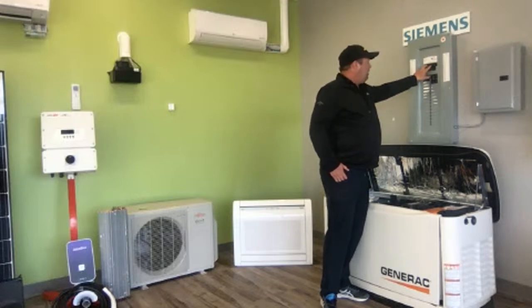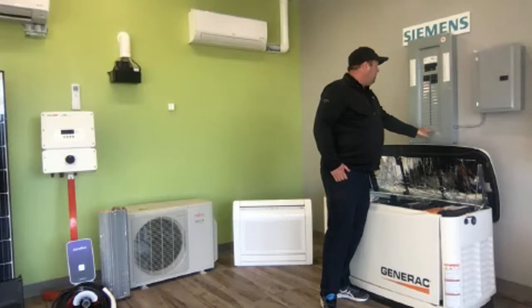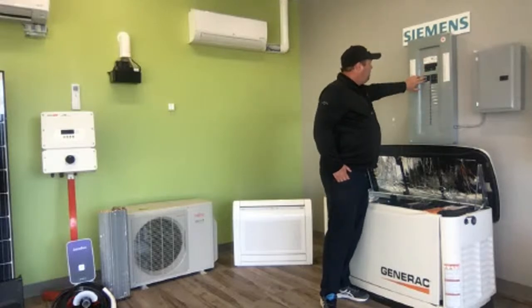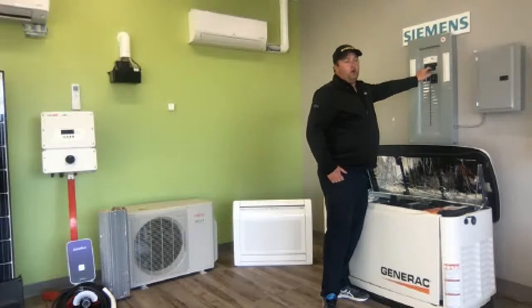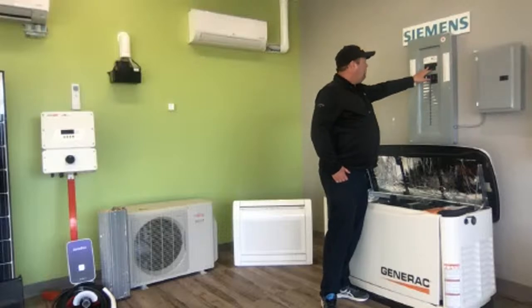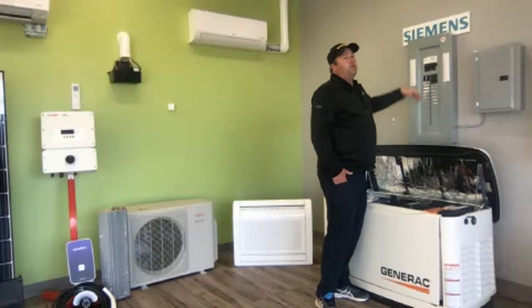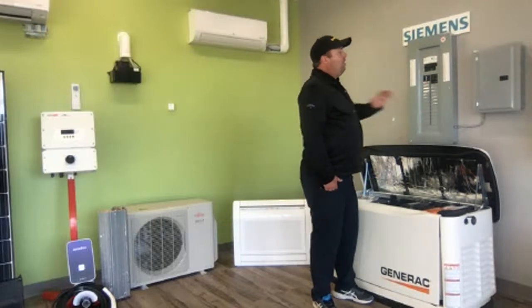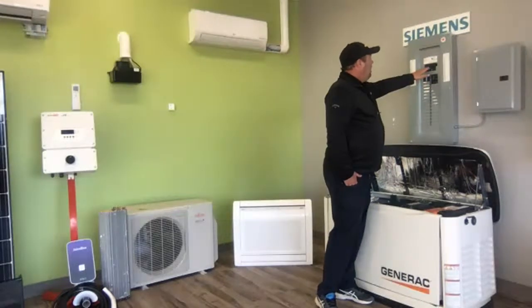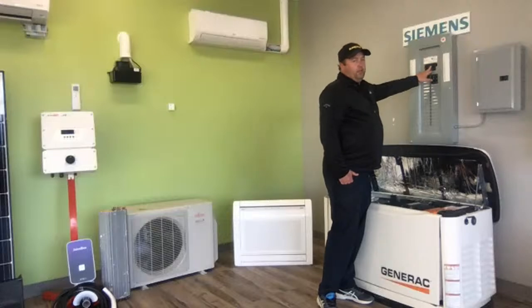This is typically at the top, sometimes you'll see them at the bottom, and every once in a while in here. On that is indicated the actual amperage of the system. Now, sometimes people think, well, this has 200 and this has 200, therefore it's a 400 amp service—that is not the case. This being 200 and this being 200 means it's a 200 amp service.